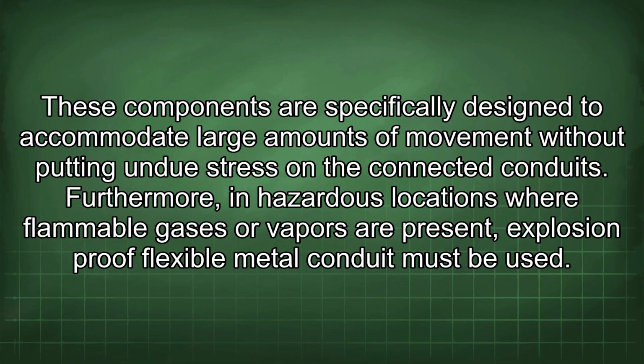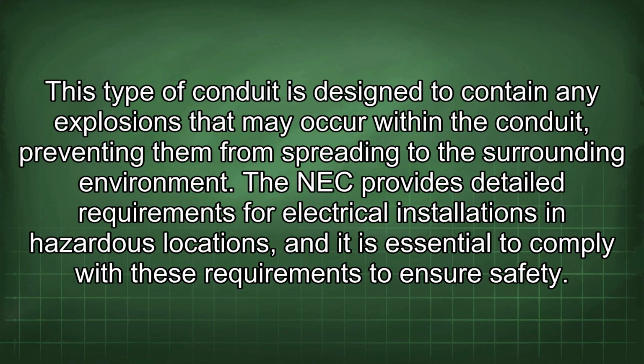Furthermore, in hazardous locations where flammable gases or vapors are present, explosion-proof flexible metal conduit must be used. This type of conduit is designed to contain any explosions that may occur within the conduit, preventing them from spreading to the surrounding environment. The NEC provides detailed requirements for electrical installations in hazardous locations, and it is essential to comply with these requirements to ensure safety.